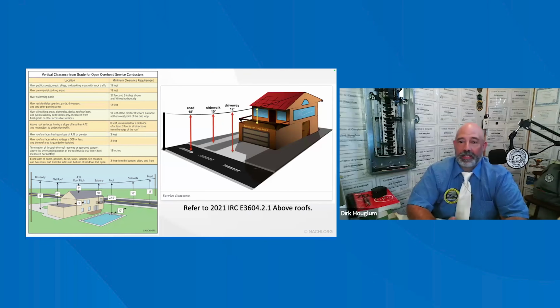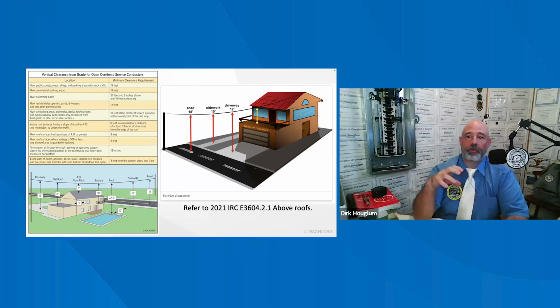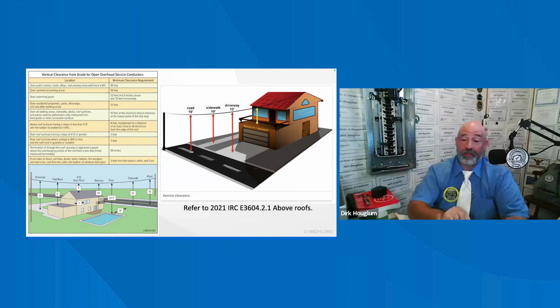There is an exception for low slope roofs or flat roofs, which a surface is accessible to pedestrians such as a balcony or deck. Overhead service conductors supported on or the cable together with the grounded bare messenger wire, above a roof surface subject to pedestrian traffic must have a vertical clearance of at least 10 feet or 3,048 millimeters.